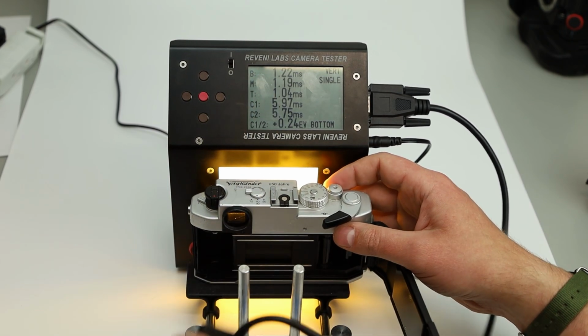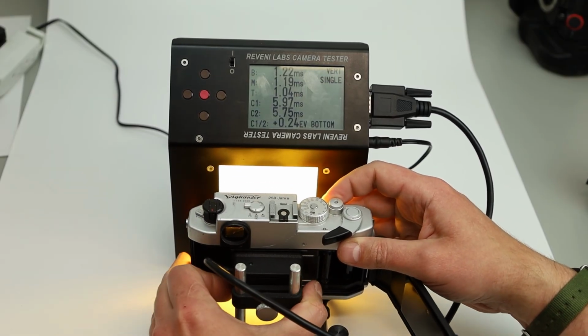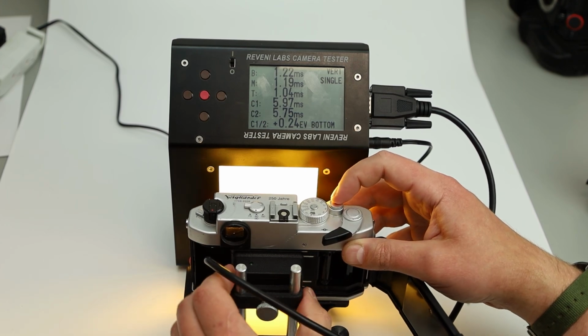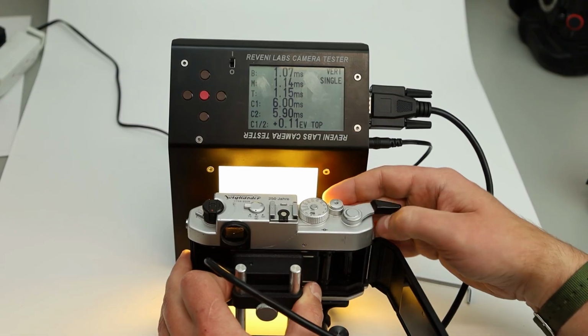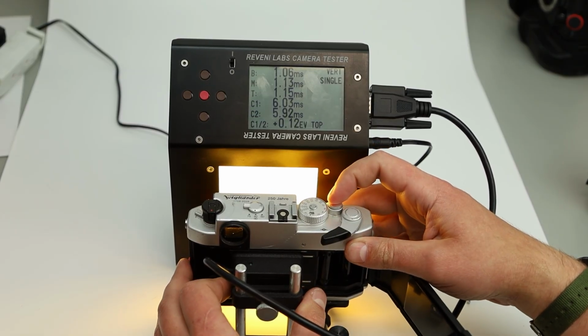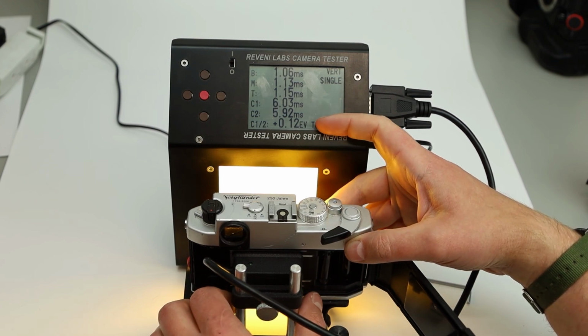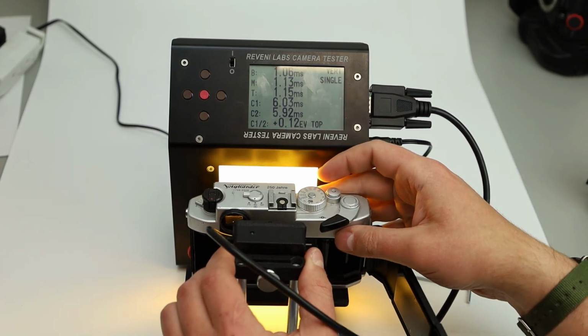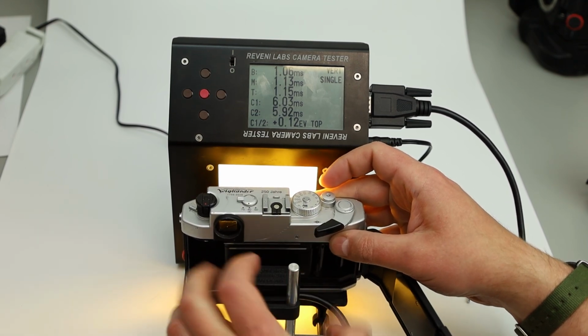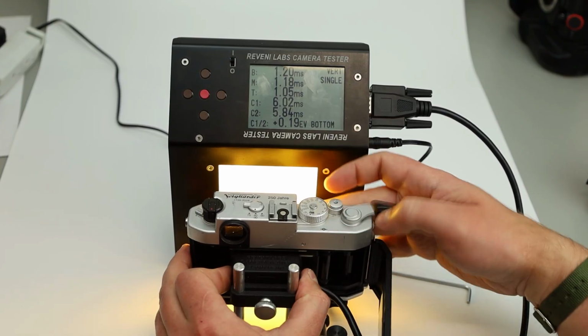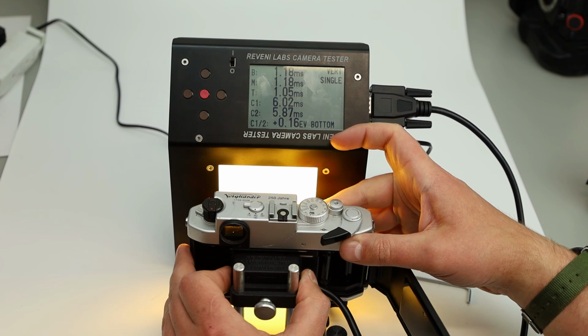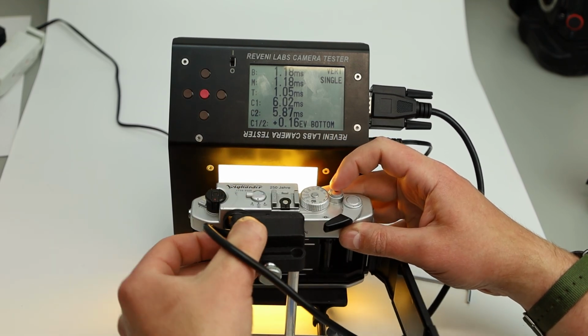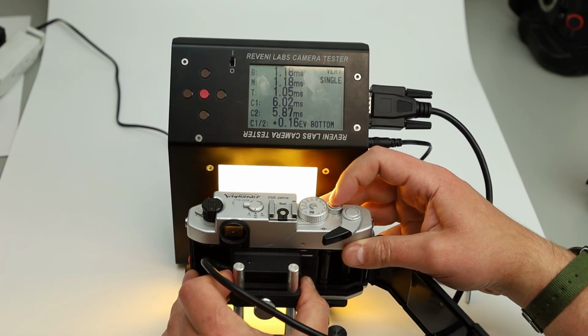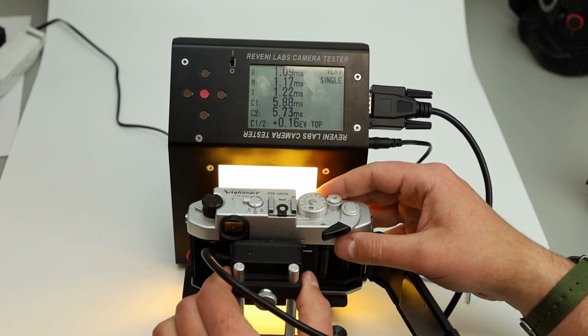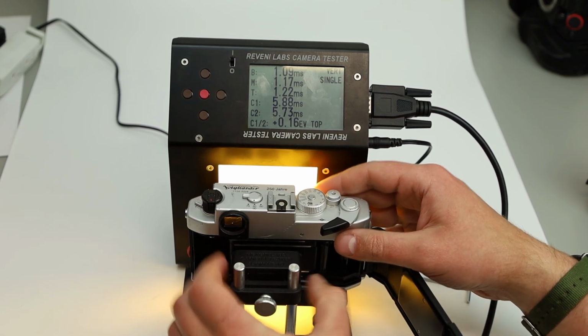I'm going to try flipping the sensor over like I did during the balancing test. See if the error flips or if the error remains the same. And the error mostly flipped. The numbers changed a little bit, but the number at the top here is now lower than the number at the bottom. It went from 0.16 error bottom to 0.16 top. So the error is flipping with the head, which means the error is in the camera itself.